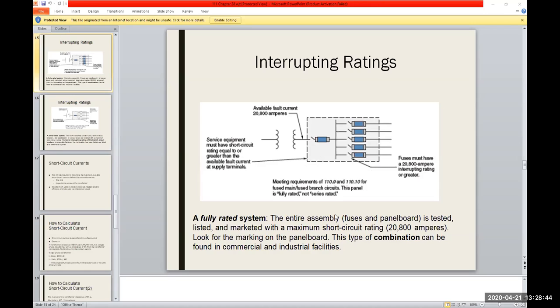And then each of the corresponding ones down below is each of your branch circuits that feed out. So it's just like a simplified drawing of your panel. So with a fully rated system, everything is tested, listed, and marked. So you don't have any qualms, everything's got a label on it, Underwriters or whatnot.